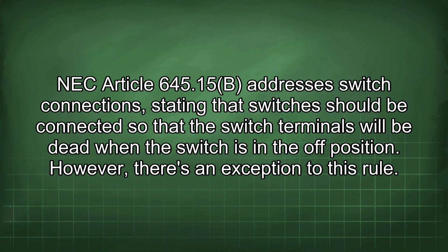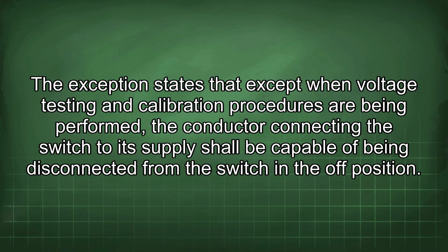NEC Article 645.15(B) addresses switch connections, stating that switches should be connected so that the switch terminals will be dead when the switch is in the off position. However, there's an exception to this rule. The exception states that except when voltage testing and calibration procedures are being performed, the conductor connecting the switch to its supply shall be capable of being disconnected from the switch in the off position.